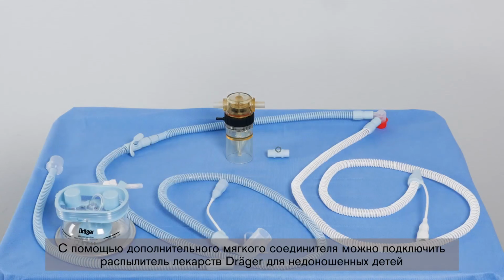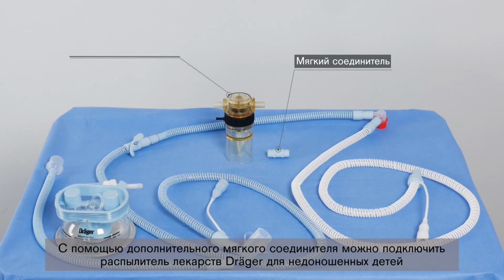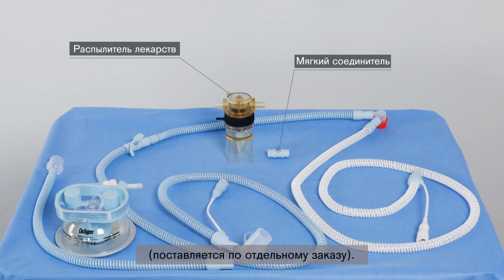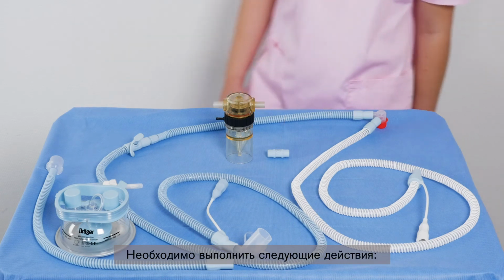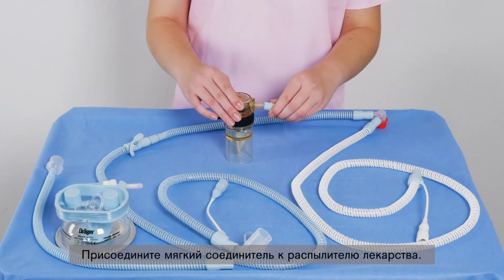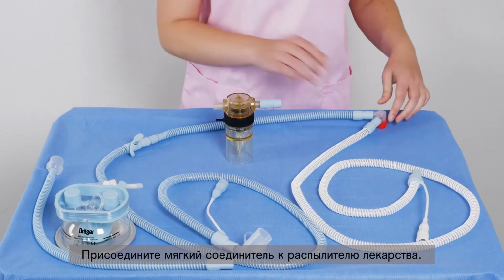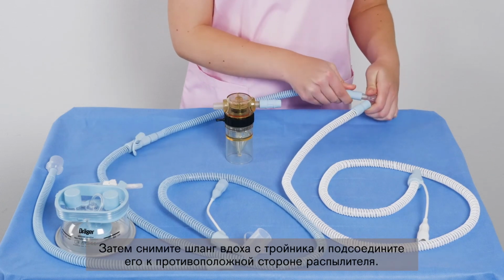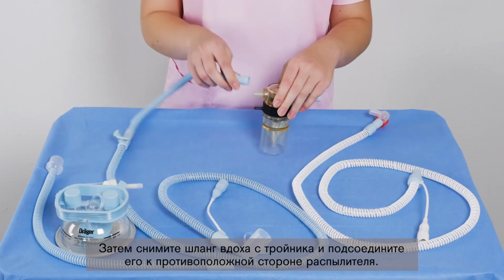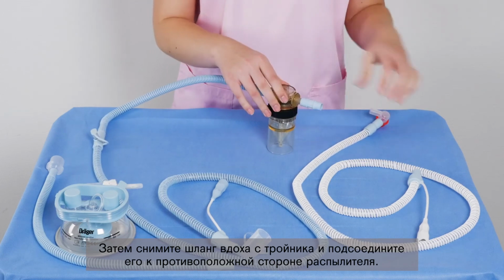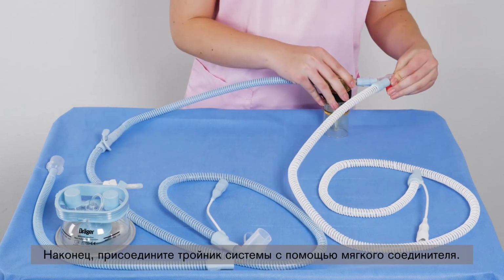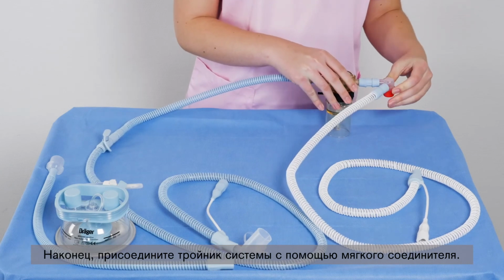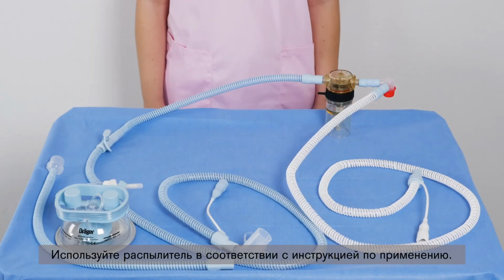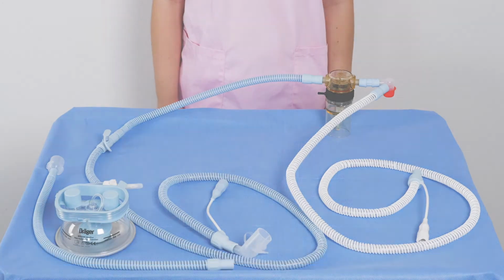It is possible to connect the Dräger medication nebulizer for premature infants by using an additional soft connector, which is available separately. Proceed as follows. Fasten the soft connector to the medication nebulizer. Then remove the inspiratory hose from the Y-piece and connect it to the opposite side of the nebulizer. Finally, connect the Y-piece of the system using the soft connector. Use the nebulizer according to the instructions for use.